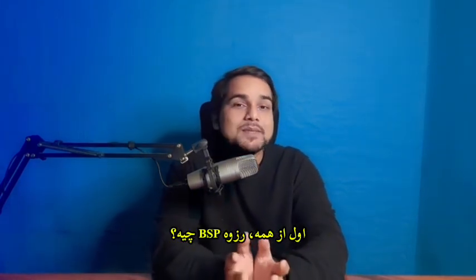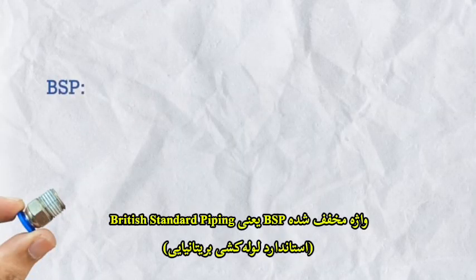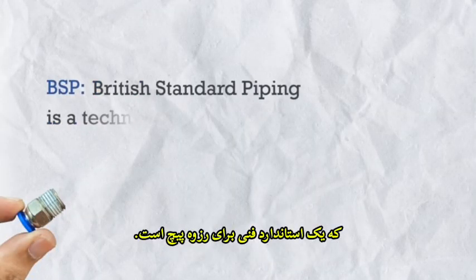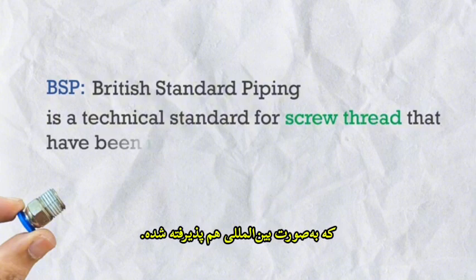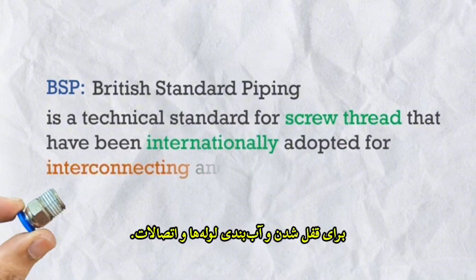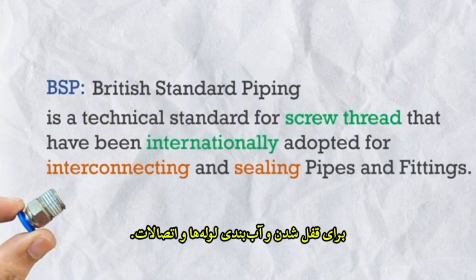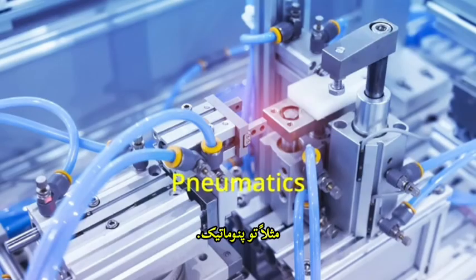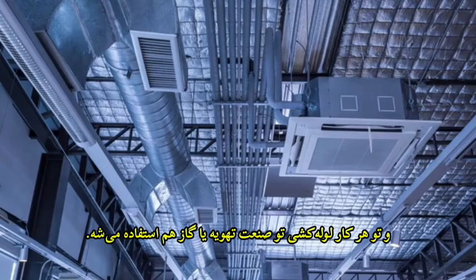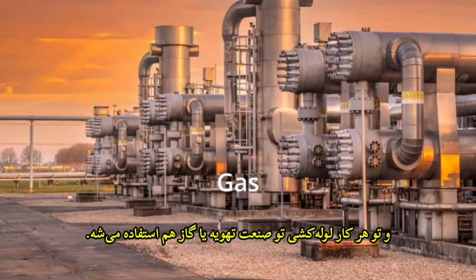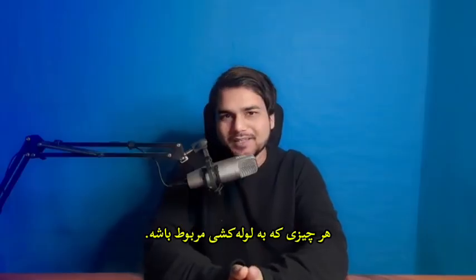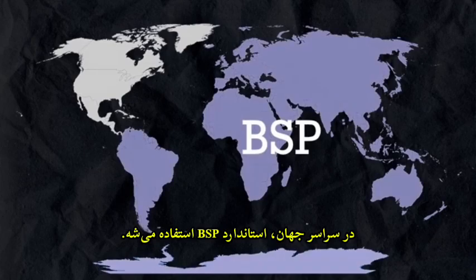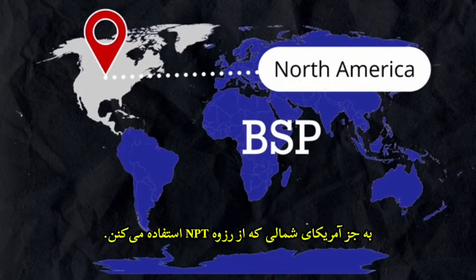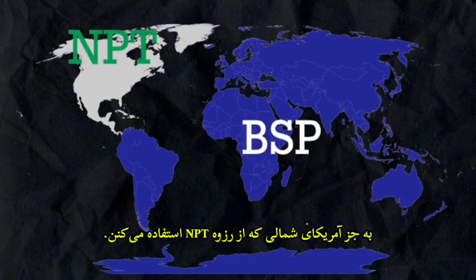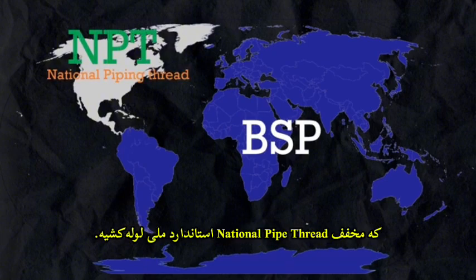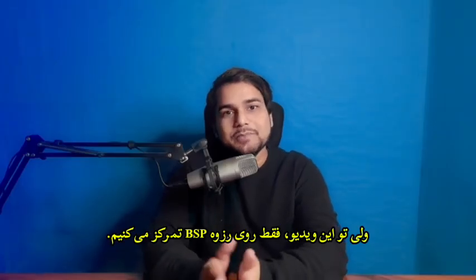So first of all, what is the BSP thread? BSP, British Standard Piping, is a technical standard for a screw thread that has been internationally adopted for interlocking and sealing the piping and fittings. For example, in pneumatics, in hydraulics and any piping work, in the HVAC industry or in the gas industry, anything related to piping in the whole world, the BSP standard is used. Except in North America, they use NPT thread, National Pipe Thread standard. But in this video, let's focus on only BSP thread.